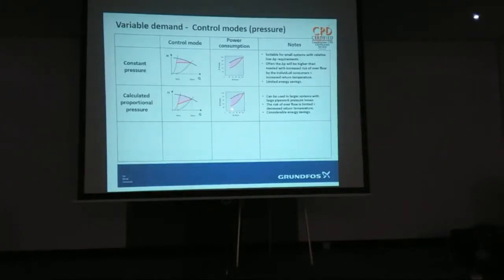That's ideal where most of the resistance is in the distribution pipework. And as long as that point there is getting your minimum flow to the furthest point in the system, that's great. It'll work fine. It's a bit of a compromise, but it works fine.